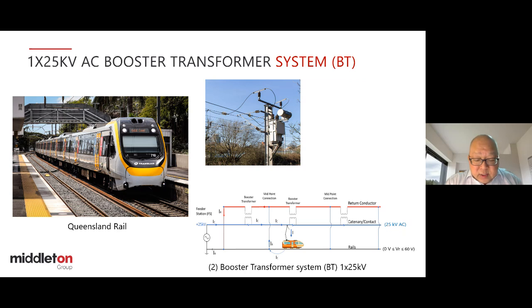So what are the pros of this system? 50 Hz leakage current is now confined and controlled. The action of the BT pulls the rail current and the 50 Hz leakage current out of the earth to the aerial return conductor via the midpoint connector, those blue vertical lines, and returns it to the feeder station via the secondary winding of the booster transformers. The current in the return conductor and the overhead line produce opposing magnetic fields and cancel each other, thereby improving the EMC performance, and is better than the rail return system.